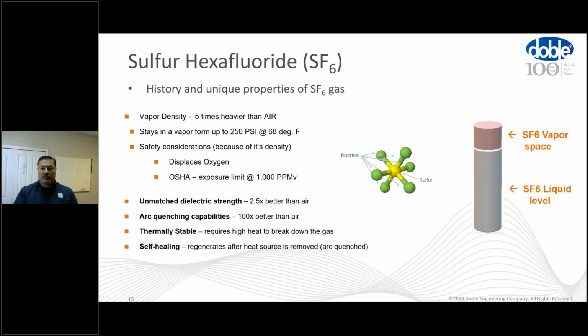Times heavier than air, which is really important because of its density. It will begin to liquefy at 250 psi at 68 degrees Fahrenheit. And in GIE, we're maintaining a lower pressure than that, so it works in vapor form. Because of its density, it displaces oxygen, so that is something very important. And the OSHA PEL, or the exposure limit, is set at 1,000 ppmV as a result.